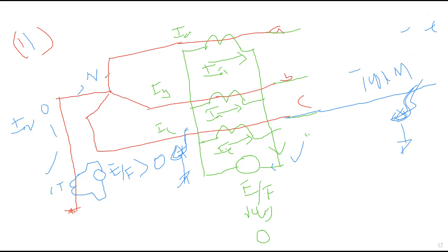It may happen that one generator is connected 100 kilometers away from the fault location, right? The generator should not trip, but due to this earth fault detection, this relay will instruct the circuit breaker to trip. That means it will isolate the generator. That is not what we want, right? Because a 100 kilometers away earth fault may be detected by some other parameters. That's not a generator side consideration, isn't it?